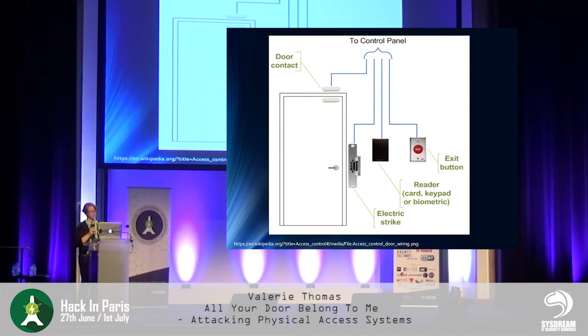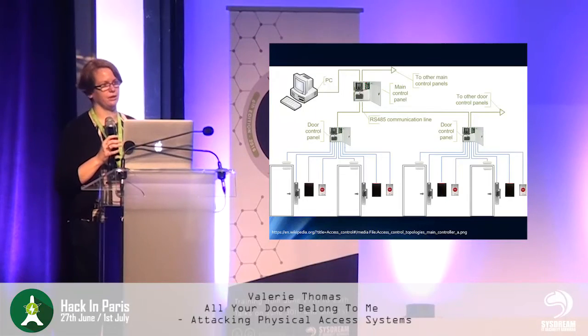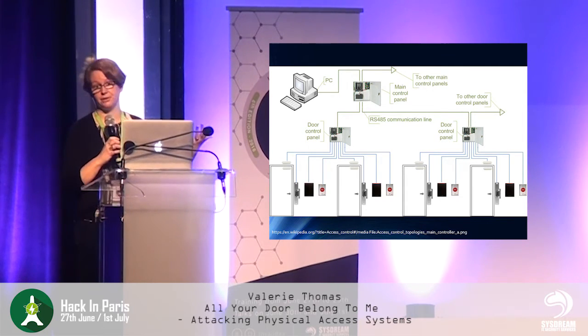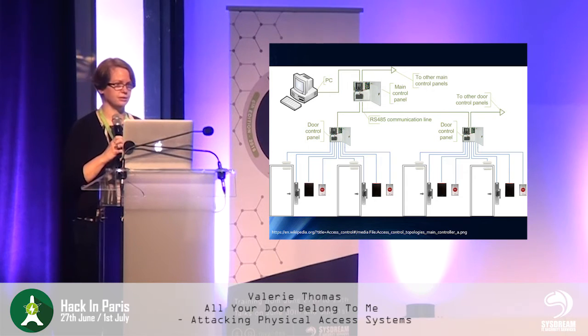So if we look at it from just a single perspective, it looks very basic. But once you start getting into multiple floors and multiple levels of the building, and you bring in things like elevators, it's a lot of inputs, and the controllers are pretty limited, even with buying the expansion pack. So you probably have at least 10 to 15 controllers in a 5 to 8-story building. So it's definitely not just one device that's sitting in the closet somewhere. We have 15 devices that are in closets and under desks and in all random areas of the building.